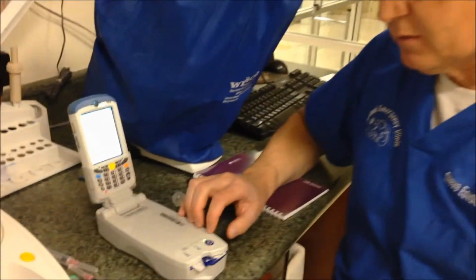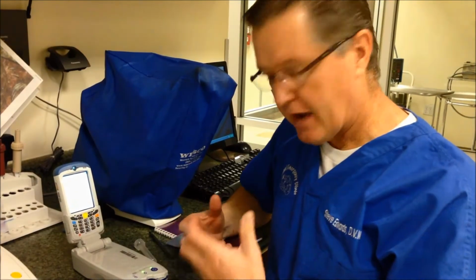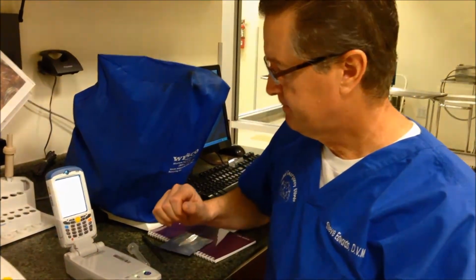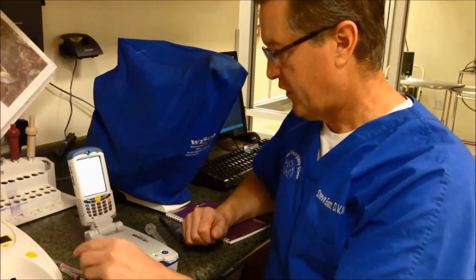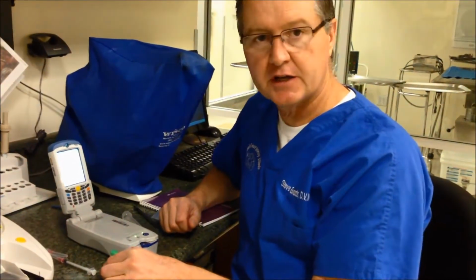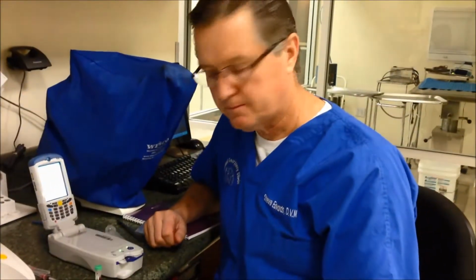It takes 190 seconds for the machine to finish up calibration. We have about 8 minutes from the time we put the cartridge into the machine to when we have to put in our sample. So there's not a huge rush, but it's good to have your blood ready to go and things set up. So we've got about another 130 seconds, so we'll pause the video. So the 190-second calibration that's happening once I put the cartridge in is about finished.